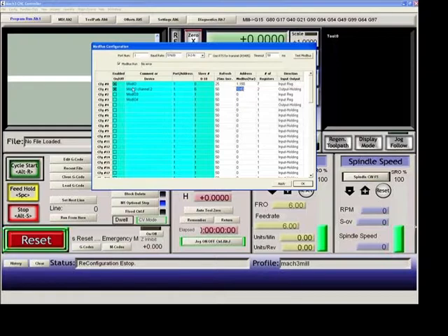So here we have, basically I'm doing 2 operations. Every 25 milliseconds, I'm sending 7 registers from the PLC, or Mod I/O in this case, into configuration 0. And every 50 milliseconds, I'm sending 2 registers from configuration 1 to the Mod I/O on address 1040. So using this screen, you can set up to 64 different configurations of Modbus data. And each configuration has 127 bytes of data, or words of data maximum, that you can use.